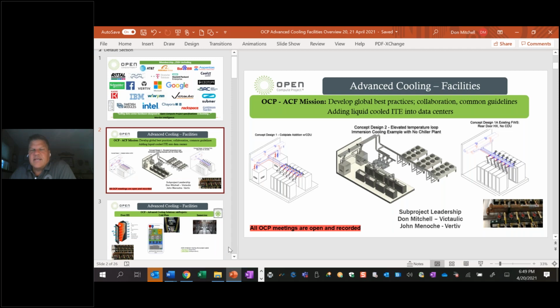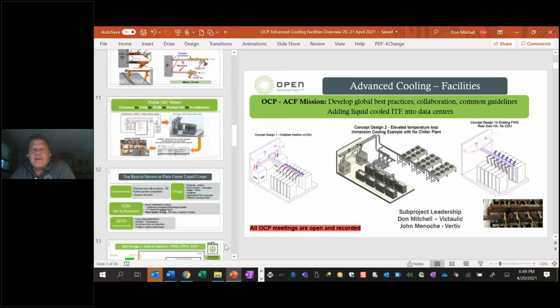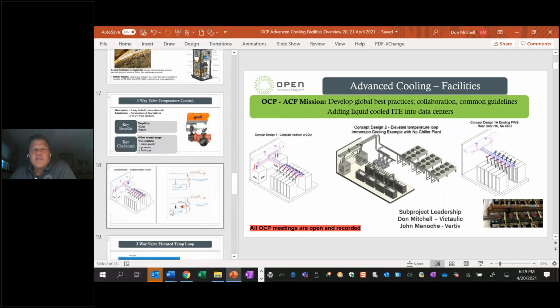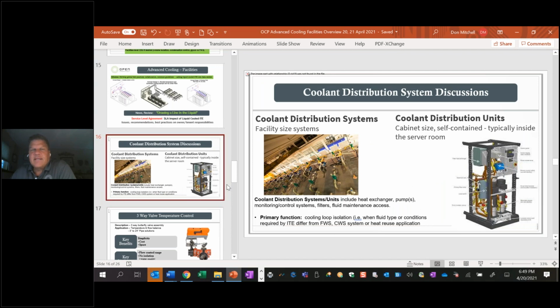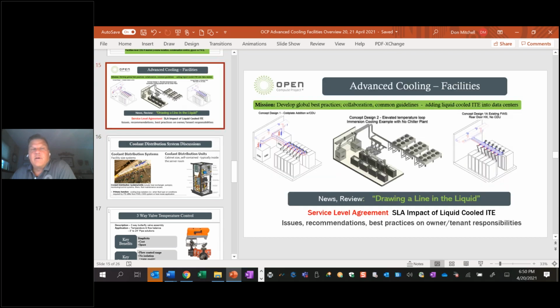One of the discussions that came up, we'll jump back and forth, was this concept of coolant distribution units. Some people ask, what is a coolant distribution unit? In some data centers, people use coolant distribution systems where the entire facility has pumps and heat exchangers, which may connect you to some cooling source. For example, if using a seawater cooling solution, you may have a heat exchanger that taps off and runs different loops. A lot of the ITE people with liquid cooled IT are coming up with smaller units, in form factors for racks, at the end of a row of racks, or they may put a little room here, okay?